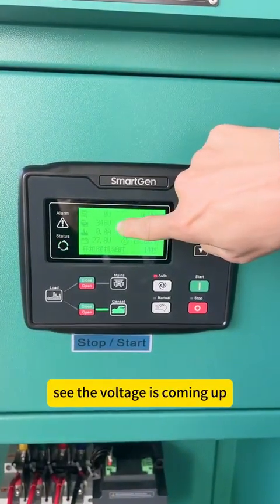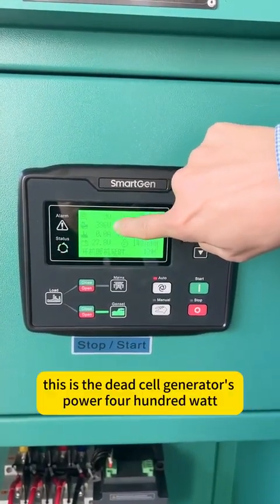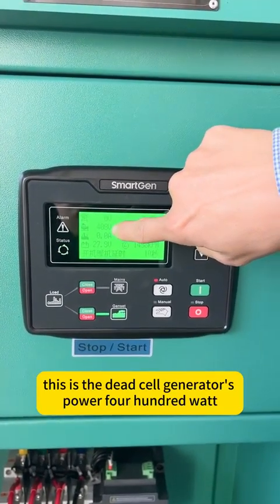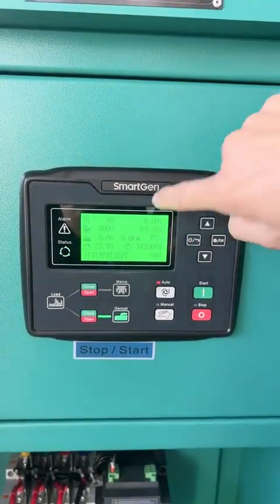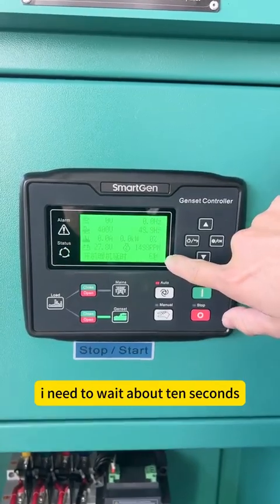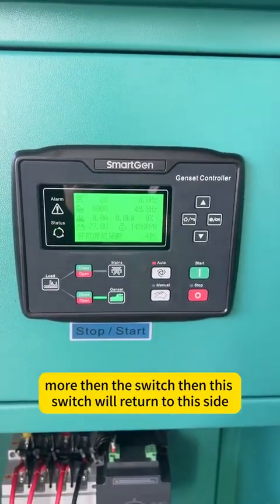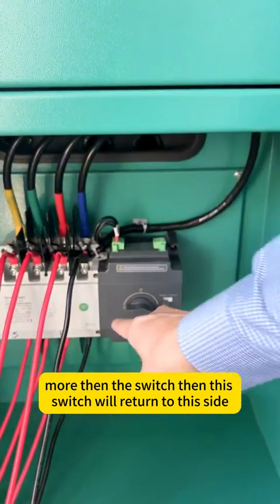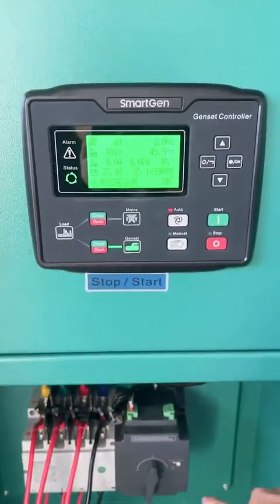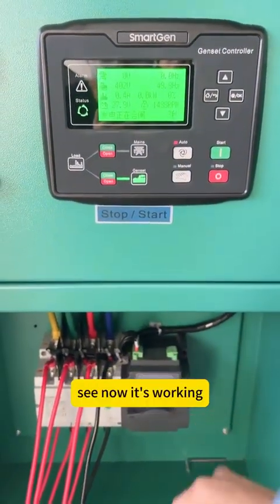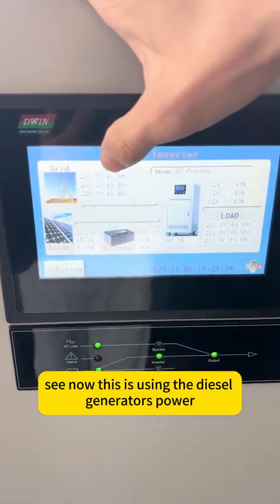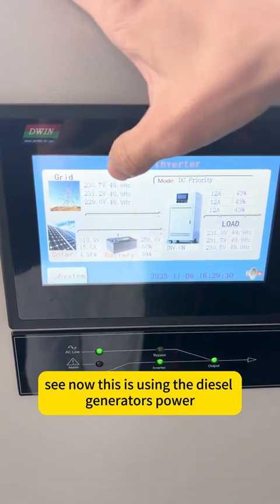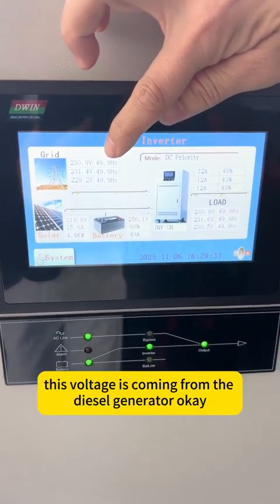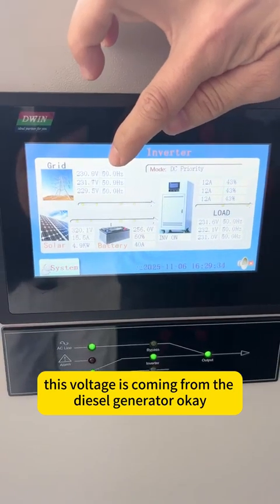See, the voltage is coming up. This is the diesel generator's power, 400 volts. I need to wait about 10 seconds more. Then this switch will return to this side. See, now it's working. Now this is using the diesel generator's power. This voltage is coming from the diesel generator.